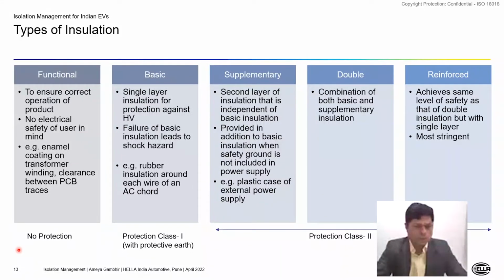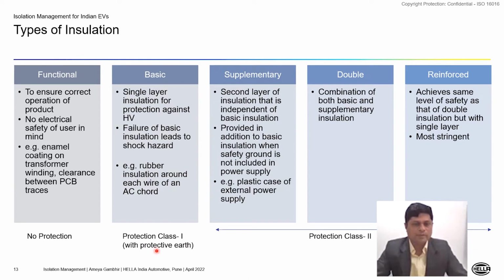There is no protection of the user in mind. Then we come to basic insulation: single layer insulation for protection against high voltage hazard, for example rubber insulation around each wire of an AC cord. This comes under class 1 of protection along with protective earth. So most of the equipment we use has basic insulation.